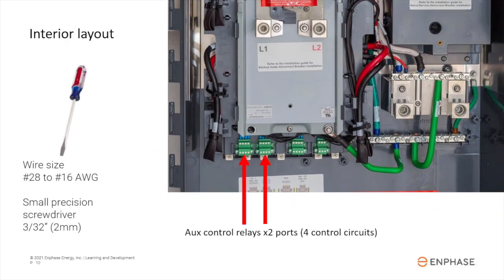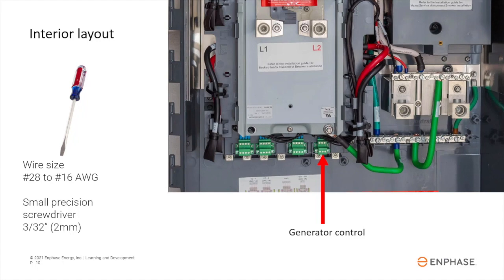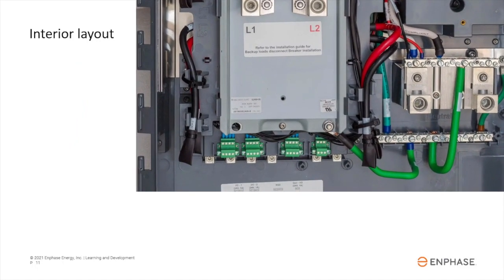The system includes small wire connectors with the literature kit. The left two ports can control up to four load control or PV-shedding circuits. The rapid shutdown port is where the external RSD switch is wired into. The last port is dedicated to remotely controllable generators. The metal wire input terminals are where you must land the microgrid power sources: battery storage, PV-AC combiner, and generator input terminals.